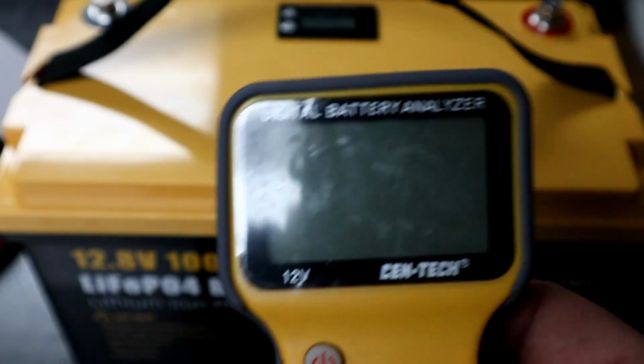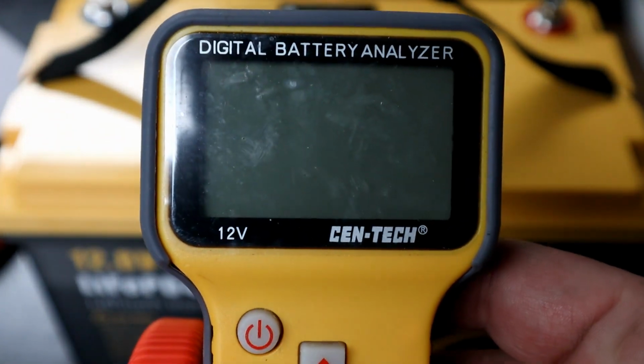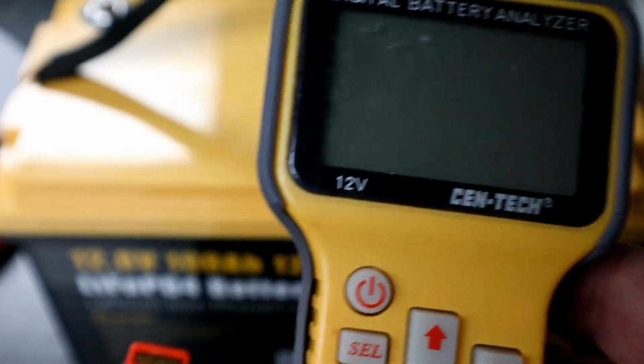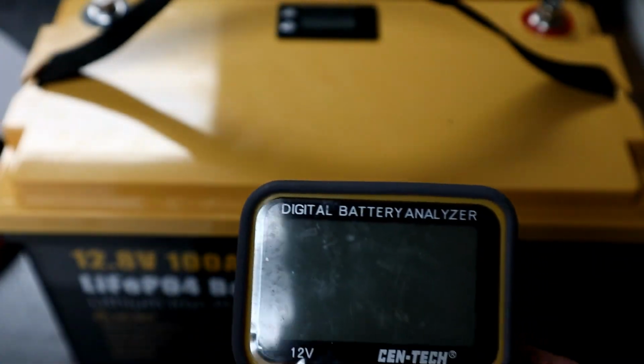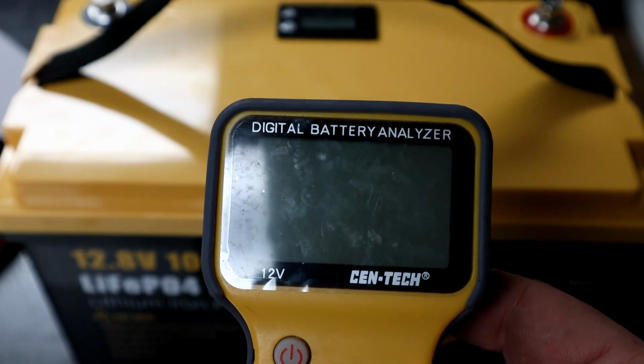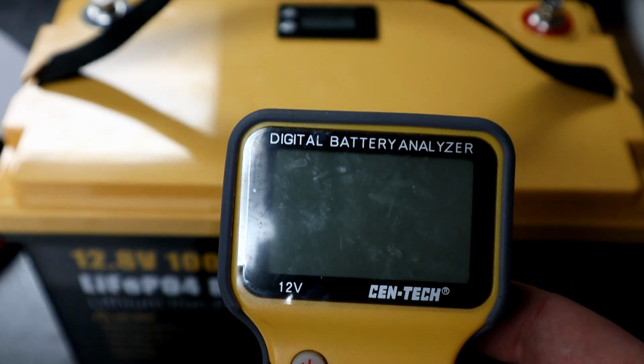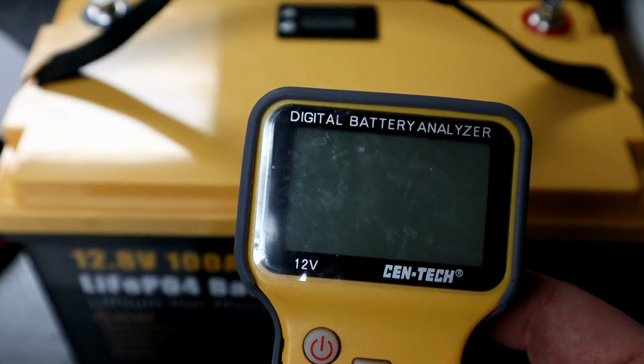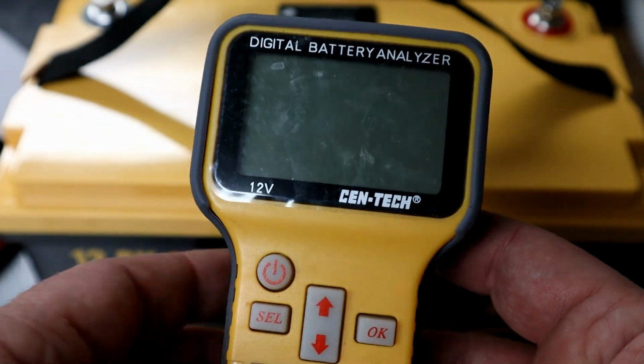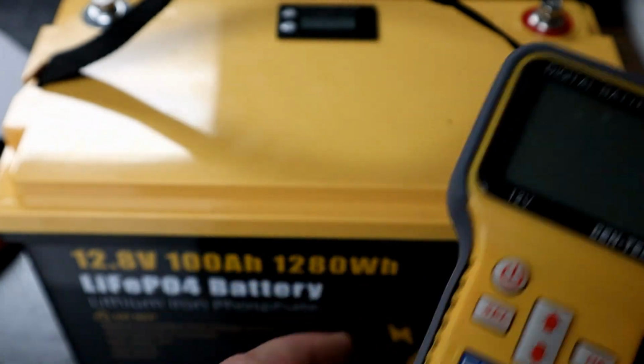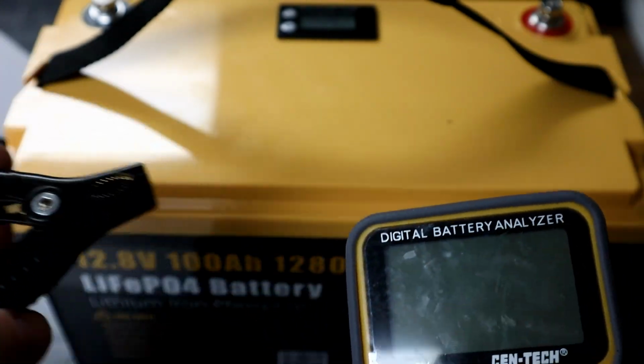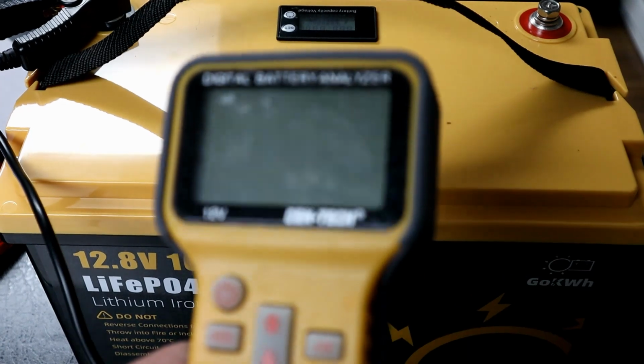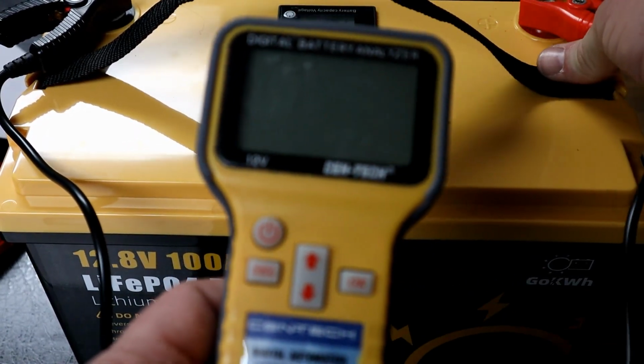Alright, our load test is complete, so we're going to move on to phase 2. We're going to use this digital battery analyzer to check out the battery. What this device does is give us an overall battery capacity, as well as checking the voltage, cold cranking amps, and internal resistance of the battery. It hooks up with these simple little clips, 1 and 2. And we'll hit the power button.